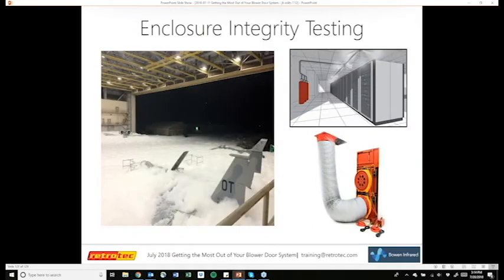Enclosure integrity testing. This is actually a big side of Retrotec, where we have systems designed just for this. What this refers to is the fire industry. So in a lot of cases, you have rooms that have items in there that cannot get wet, such as a server room with computer servers inside. So instead of having a water system, you have a dry chemical system. And before you use a blower door, a lot of times you would just have to discharge it to see what would happen. A lot of times this agent that comes out of this assembly comes out at such a high pressure that it can be really destructive to what's inside, as well as to the walls and ceiling itself. And so a way to do that is you have to have these walls vented a certain way towards the top, and you can use a blower door to make sure that that agent is going to drop and behave the way it's supposed to without being destructive.